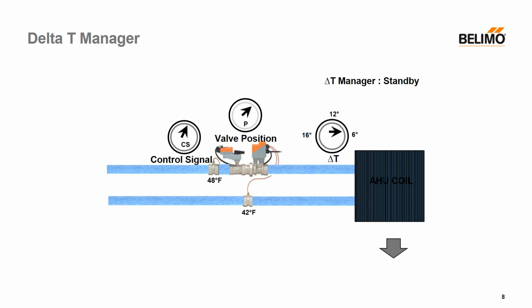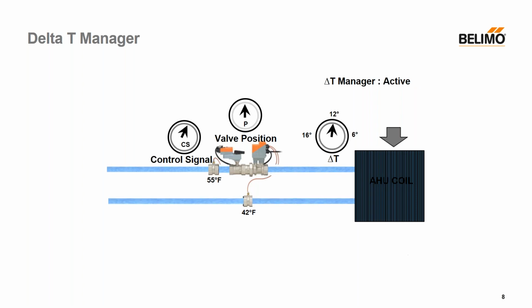The valve sees this happen and has some logic that says I need to take over. So delta T manager goes active. We can see the control signal is not moving. The valve position is moving, and the delta T has increased. We've gone back from that 6 up to where we want to be in that 13-ish range. So water is now coming in at 42, again leaving at 55. This is what we're doing. We're controlling that delta T to make sure we're efficiently using the water in our system. In the example we're referring to, we're eliminating the overflow and not paying just to pump water around our system.